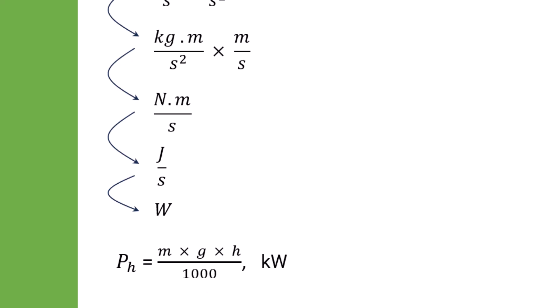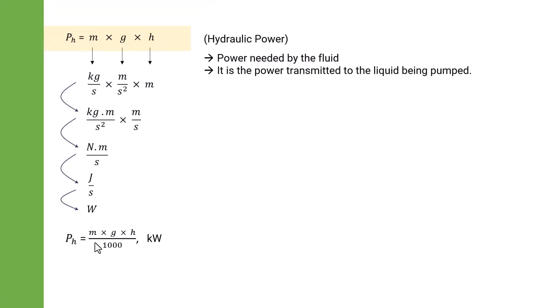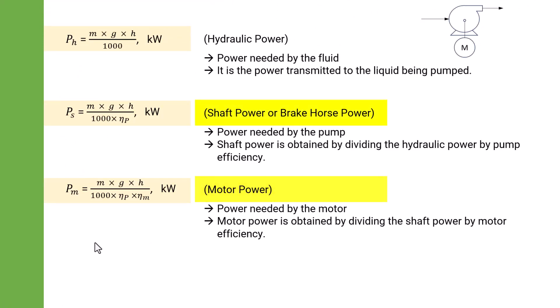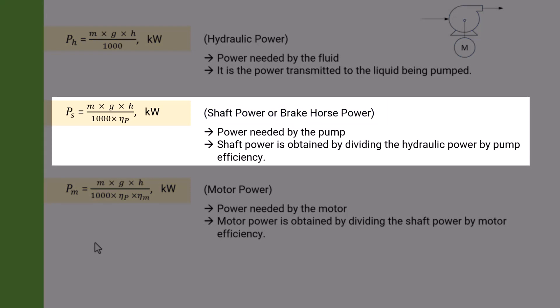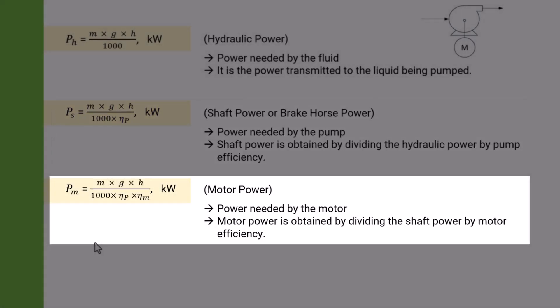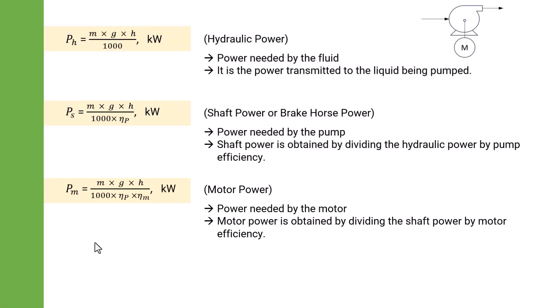Note that hydraulic power does not account for pump efficiency or motor efficiency. To account for those we have shaft power and motor power. Shaft power, also known as brake horsepower, is the power needed by the pump. It is obtained by dividing hydraulic power by pump efficiency. Motor power is the power needed by the motor, obtained by dividing shaft power by motor efficiency. This is the actual electricity consumed by the motor to run the pump. Now let's use these formulas in an example.